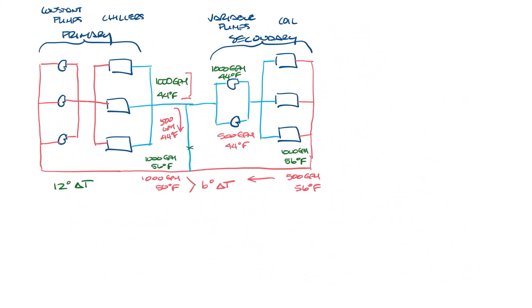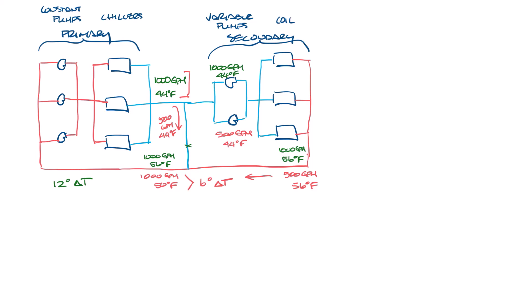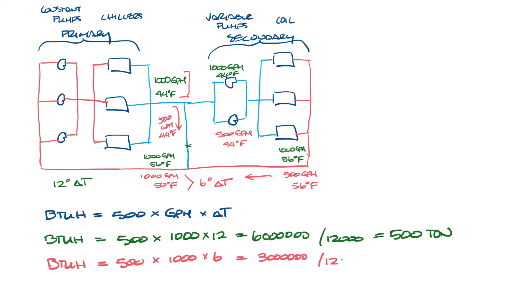So let's move this up a little. If we look at this in terms of BTU hours, BTU equals 500 times GPM times delta T. So for the first example, we'll have BTU equals 500 times 1,000 times 12, which is 6 million BTU. And if we divide that by 12,000, that gives us 500 tons. And for the low delta T example, we have BTU equals 500 times 1,000 times 6, and that's 3 million. We'll divide that by 12,000 and get 250 tons. So basically we're getting 250 tons of cooling out of our 500 ton chiller.